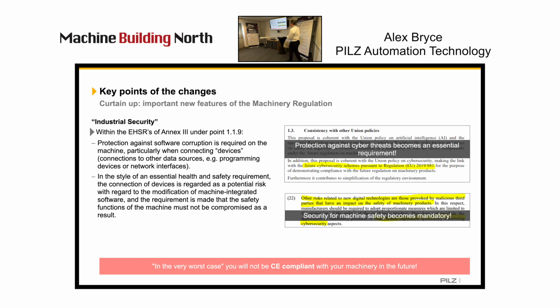Under 1.1.9, which we'll look at a bit more, it talks about protection against cyber issues. Now, a cyber issue might be an internal member of staff with a thumb drive that goes down and puts something in to change a parameter. That thumb drive might have been infected with something from somewhere else, and he's automatically transferring that to a machine, which could have a catastrophic effect.